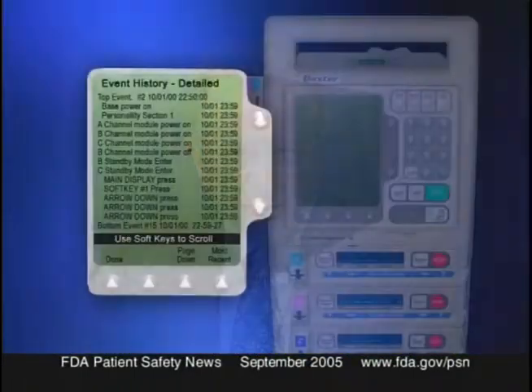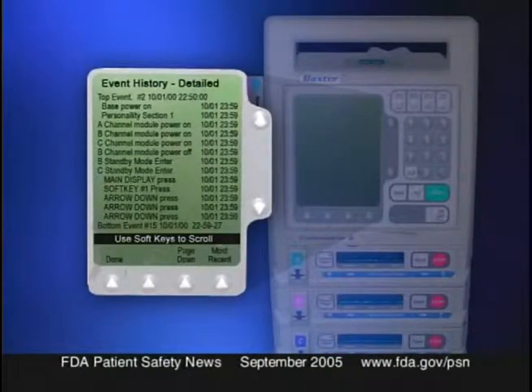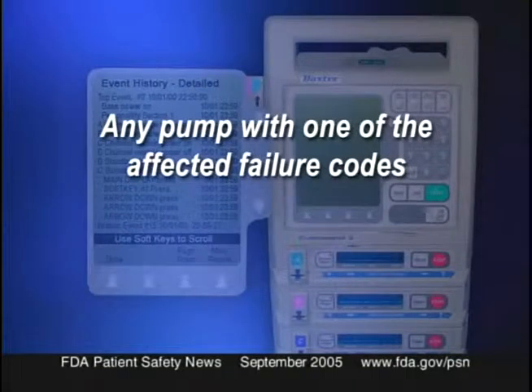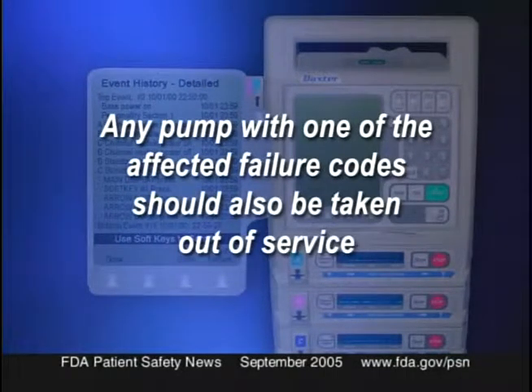Review the event history of every Colleague pump still being used. Any pumps that have exhibited one of the affected failure codes in the past should also be taken out of service. Since these failures may occur during an infusion, have a contingency plan to minimize disruptions of infusion therapy, for example, have a backup pump available. And finally, the company says you should consider not using these pumps in situations where a malfunction could have life-threatening results or where a replacement pump is not available.